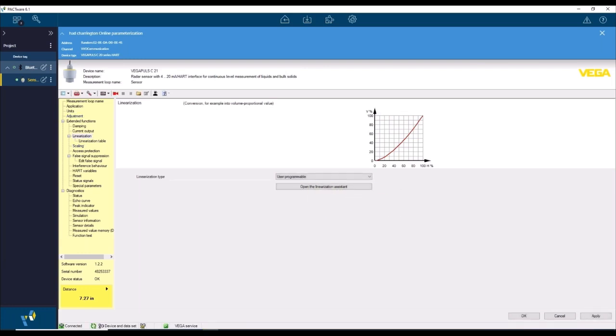Now, also what you can do, the system's now set up and ready to go. If you were to send the output from the C series to one of our signal conditioners, the 800 series signal conditioners, these signal conditioners have relay output and they have current output. So what you can now do is bring this information into the signal conditioner, and now you can use it also for pump control. There you go. So that's the quick and easy for a Parshall flume setup.